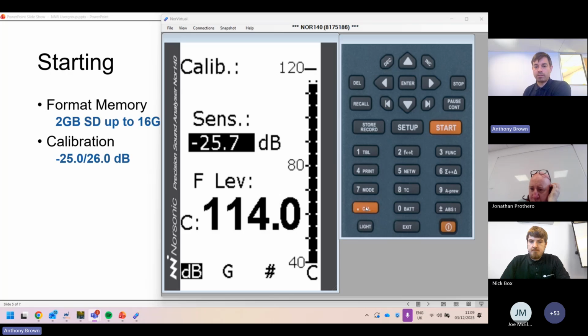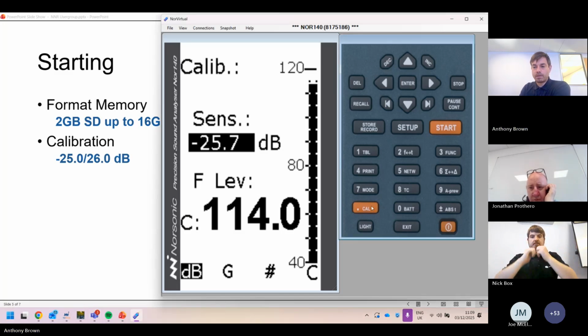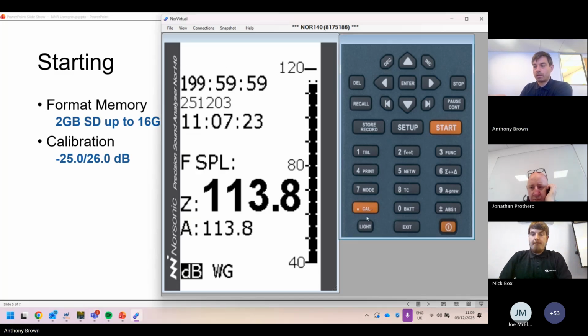And then we adjust it by using the INC or the DEC key, these two keys here, until we get to 114. And then once you're happy with that, you just press the orange CAL button again at the bottom to go back. And then you can take the calibrator off the end of the meter.